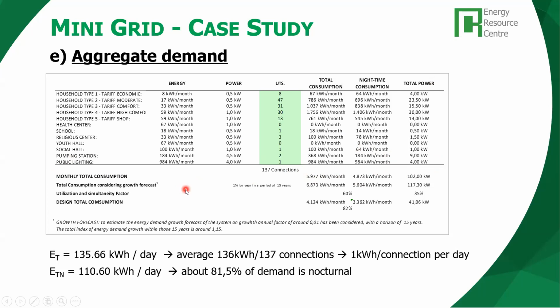Now we introduce the growth factor, okay? So 1% per year in a period of 15 years. So that's an aggregate of 15%. That's what we introduce here to increase the expected demand after 15 years. So you can see there's an increase, almost 7,000 kilowatt hour per month, 5,600 kilowatt hour per month nighttime consumption, and the total power with the growth factor, 117 kilowatt. So this is what we expect to have as a gross demand after 15 years because of the growth.